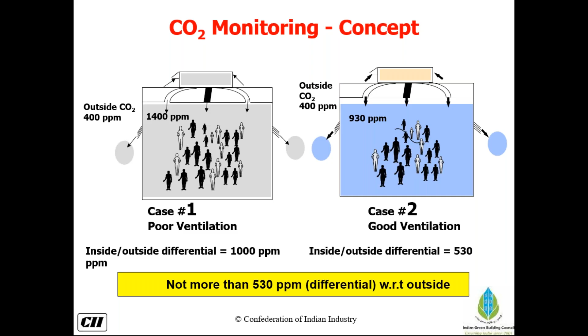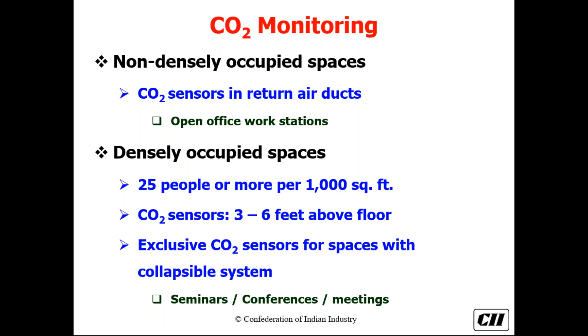In non-densely occupied spaces, you could have CO2 sensors in your return air ducts, in office areas where you have pantries or movement areas. Whereas for densely occupied spaces, with 25 people or more per thousand square feet, you need to have these sensors between 3 to 6 feet above floor level in the working plane, the working zone, and also exclusive CO2 sensors for spaces with collapsible systems, such as seminar, conference, and meeting rooms. Now, this could be the same for the other parameters as well, whether you're comparing PM particles or measuring ozone or other things, because each of these parameters is unique and has a unique way of being dealt with. Of course, the CO2 monitoring that you see here is an example to illustrate how it's done.